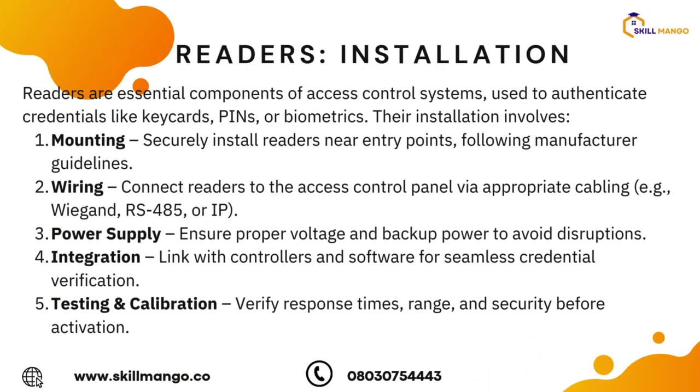Okay, so the installation is very straightforward. You just have to mount them at the designated location. Most times it has to be by the entrance door. So you just swipe your card or put your finger or your face. The signal goes to the mag lock, and the mag lock disengages and opens the door for you. You gain access. So mounting, then the wiring. Like I said, the cable they use is the Cat6 cable. That's the kind of cable we use to deploy this kind of solution.